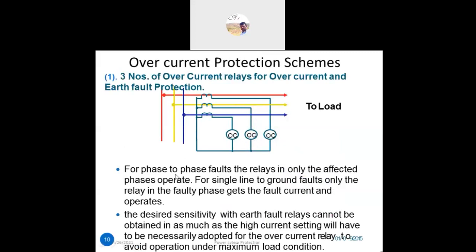For phase-to-phase faults, only the relay in the affected phase operates. For single-line-to-ground (LG) faults, only the relay in the faulty phase gets the fault current and operates. However, the desired sensitivity with earth fault relays cannot be obtained because a high current setting must necessarily be adopted for overcurrent protection.